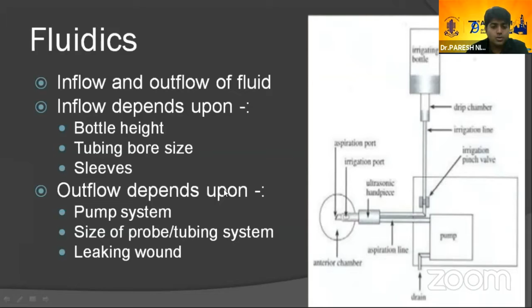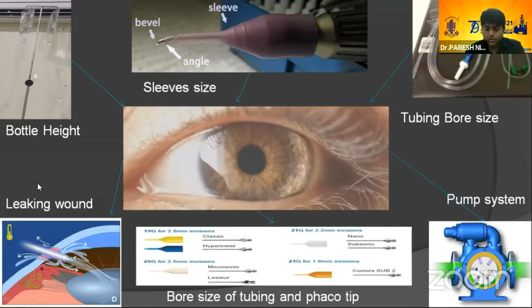The fluidics is basically the inflow and the outflow of the BSS from the eye. The inflow depends on the bottle height, or in advanced machines the irrigation pressure, the bevel size of the sleeve or the sleeve size, and the tubing system bore size. Outflow depends on the pump which we are using, the bore size of the tubing system and the phaco tip, and any leakage in the wound.